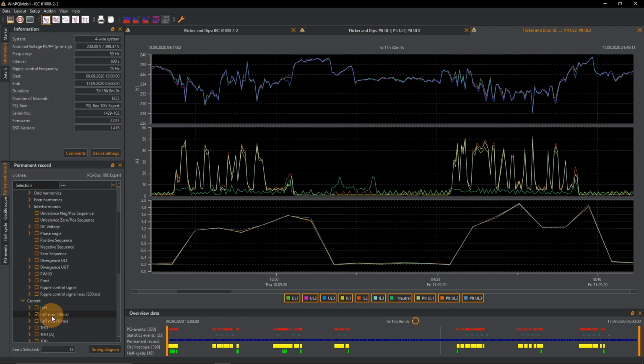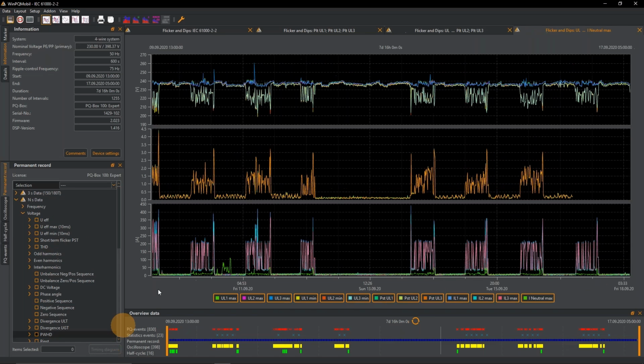And with the maximum values, I get the 10 milliseconds. So this is the so-called half period RMS value. I will get a new one every 10 minutes, and this records the highest or the lowest 10 millisecond value within my measurement period. So I will click on timing diagram, and now I will see something different.